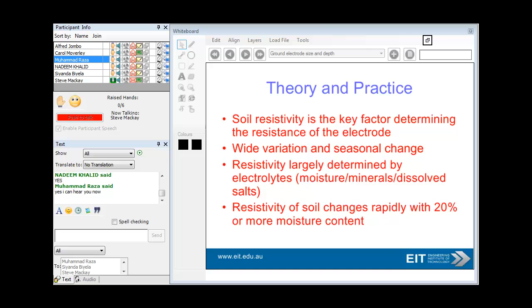The resistance of an electrode is made up of the resistance of the metal electrode, the contact resistance, and the resistance of the soil. So when you put an electrode into the soil - that's your soil there - it depends on the resistance of the electrode, the contact resistance around it, and the resistance of the soil. If you increase the diameter of the rod, making it fatter, you don't actually reduce resistance much. If you increase the length of the rod, you reduce the resistance quite significantly, by up to 40%. Obviously if you've got rock here, it's a lot more of a challenge to get it in.